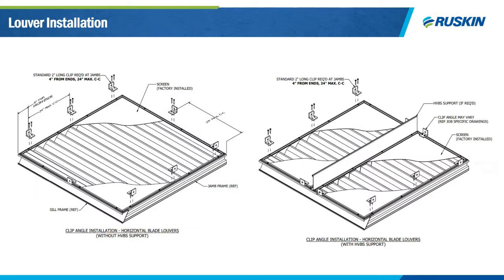Now let's talk about how louvers are going to be installed. Here you see one of the most basic installations, which probably applies to 80 to 90 percent of your applications. You see two single-section louvers — one without any blade support and one with a hidden vertical blade support to accommodate its size or wind load. Typically you'll use a 2-inch by 2-inch by quarter-inch thick by 2-inch long clip angle, mounted 4 inches from the ends of your louver and then a maximum of 24 inches on center for the remaining assemblies.